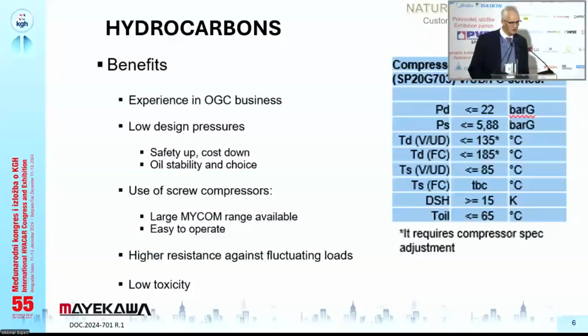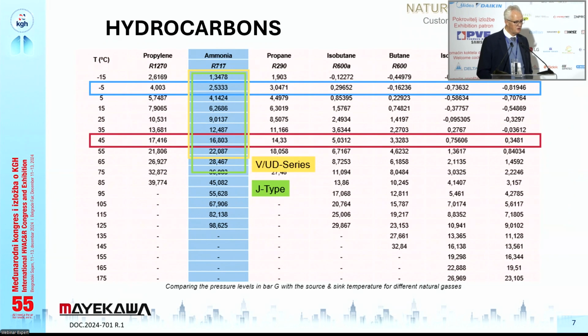I added here a table in which you can see the operating limits, and you will see that the discharge pressures, they are up to 22 bar gauge. The suction pressures are up to 6 bar gauge. The hot gas temperatures up to 135 degrees for our ranges V and UD. And for our new screw range FC, we go up to 185 degrees with necessary compressor specification adjustments. The oil temperature can be maximum 65 degrees, and the superheat on the discharge side must be bigger than 15 degrees.